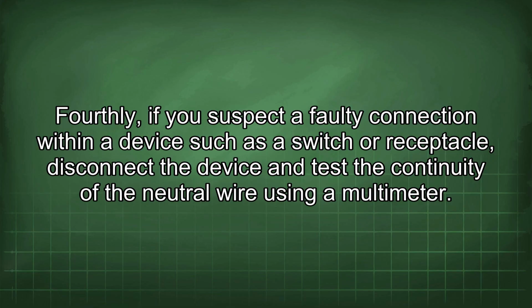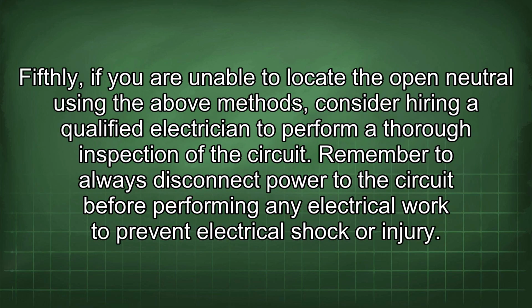Fourthly, if you suspect a faulty connection within a device such as a switch or receptacle, disconnect the device and test the continuity of the neutral wire using a multimeter. Fifthly, if you are unable to locate the open neutral using the above methods, consider hiring a qualified electrician to perform a thorough inspection of the circuit. Remember to always disconnect power to the circuit before performing any electrical work to prevent electrical shock or injury.